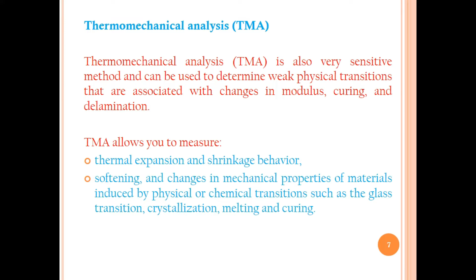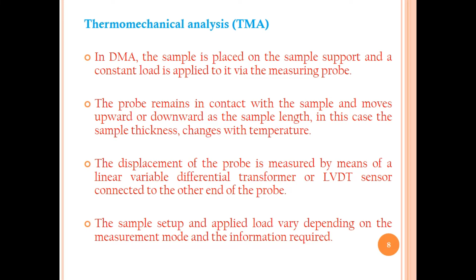In TMA, rather than DMA, the sample is placed on a sample stage and a constant load is applied to it via the measuring probe. The probe remains in contact with the sample and moves upward and downward as the sample length changes. In this case, the sample thickness changes with temperature, and that is measured by thermomechanical analysis. That is a mechanical property of the material under observation. The displacement of the probe is measured by means of a linear variable differential transformer, or LVDT sensor, which was already discussed in the DMA technique. It is connected to the other end of the probe, which is connected to the sample under investigation. The sample setup and applied load vary depending upon the measurement mode and the information regarding the sample to be obtained in the TMA instrument.